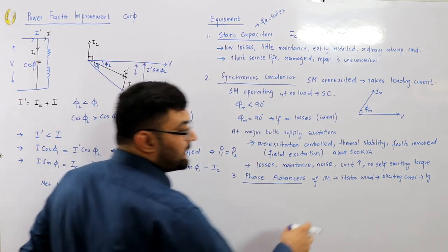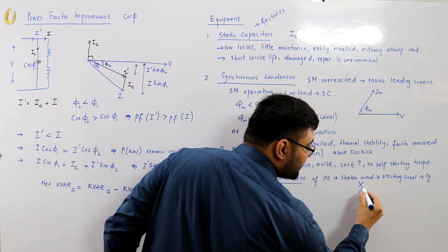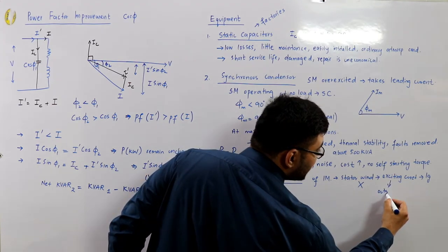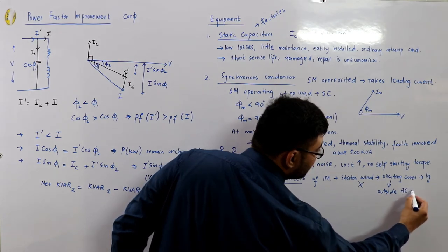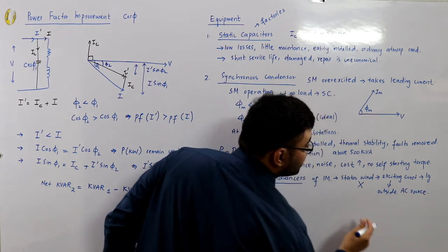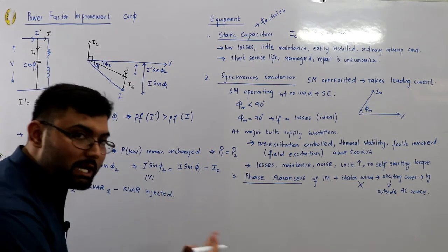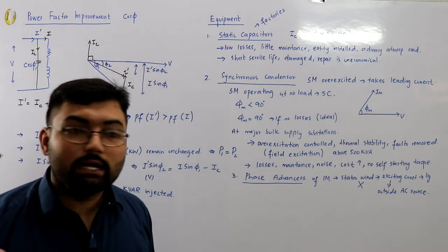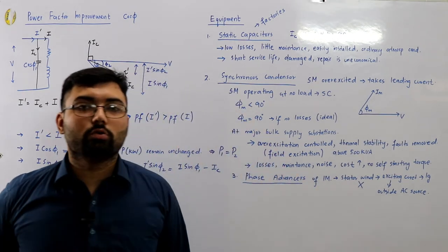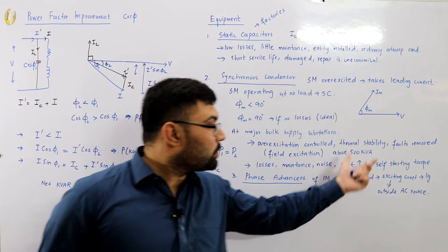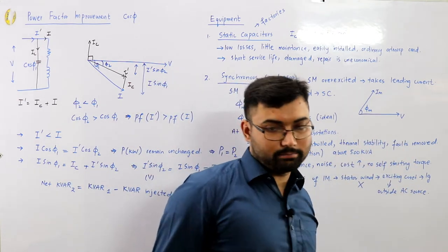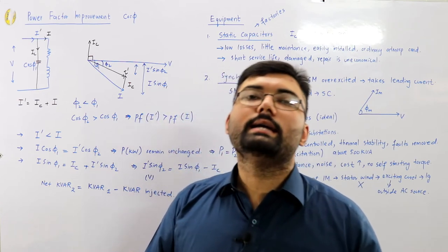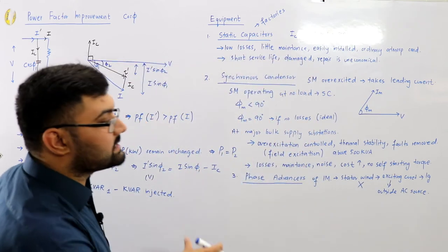So what you do is, in place of the stator winding, you take the exciting current from an outside AC source. So the stator winding would also be relieved of what? Of providing the exciting current, and the power factor would also be improved. Why? Because it would not draw that lagging current. Right? Yes. This job is accomplished by a phase advancer.